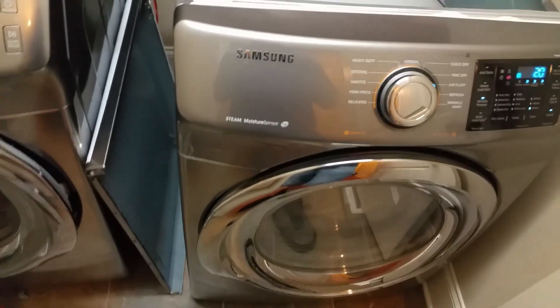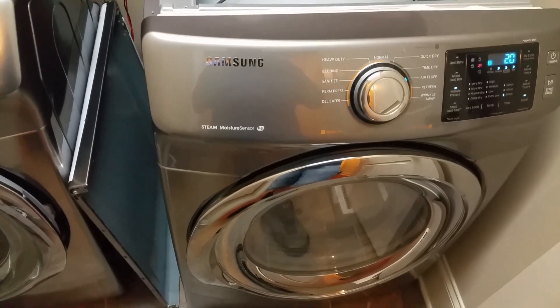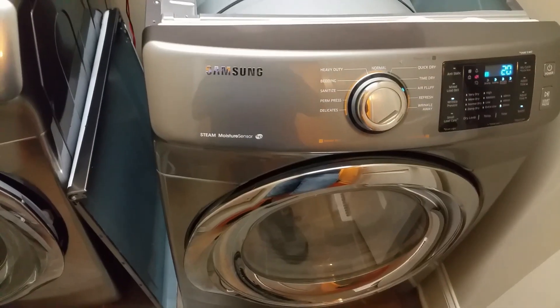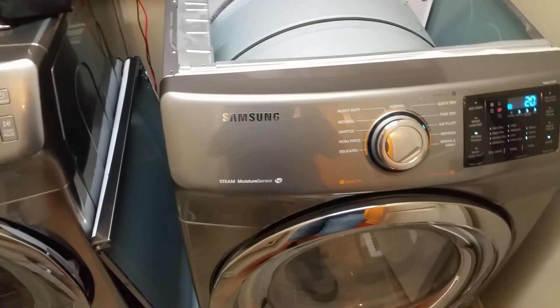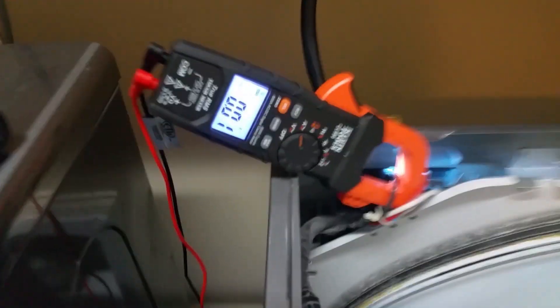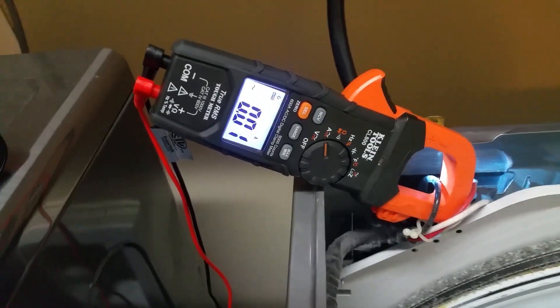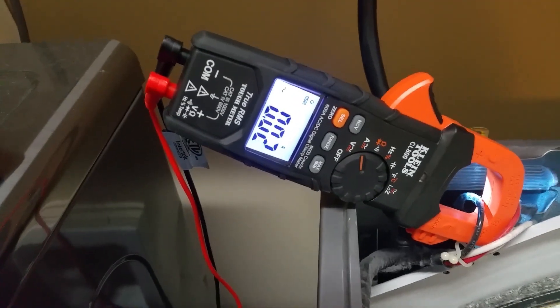We have a Samsung dryer here. The customer states that after a few seconds the dryer just stops running and they can't restart it. First thing I'm thinking is a bad motor, so I'm going to put it in air fluff mode. I've got an amp clamp on L1 and we're going to look at the current draw with no current going through the heat circuit.